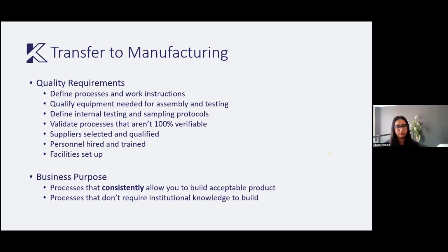That is the goal. If there are a lot of loopholes in the QMS, I actually wouldn't call them loopholes, but sorry, there's a lot of allowances in the QMS that permit you to move processes into manufacturing that don't always build good product, but it's okay as long as the bad product doesn't go out to the field. So if I come back to that, like, don't hurt patients, don't hurt clinicians, purpose of a QMS, that's really the goal of it.